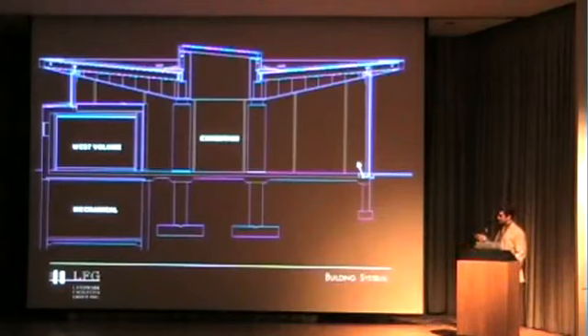The other thing is the airflow is very slow here, and as the air enters into this space, you end up with a stratification across the top layer. So down in the area where the occupants are, the temperature is just perfect for occupant comfort. But up in this upper area, it can be warmer, and thereby increasing the energy efficiency of the system.